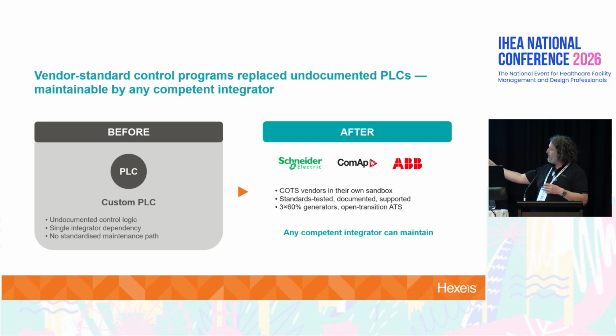So another element of the design, which Charlie asked me to mention, was he also likes to make sure that when you put in your generators, you don't do like 2 generators, you always go 3 generators at 60% each. Because that way you can take 1 generator out for maintenance and you've still got 120% capacity online. Whereas if you only have 2, you take 1 out, now you're talking about doing all sorts of fancy load shedding and contingencies in case something happens while that was happening.